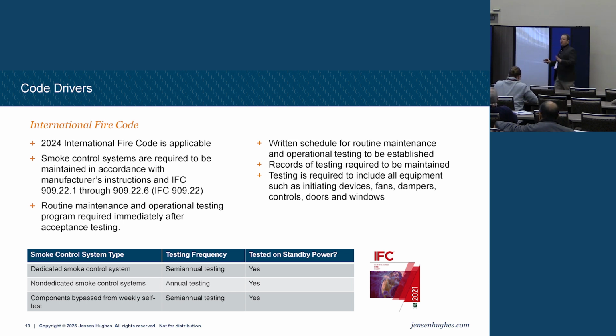Testing is required to include all the equipment, right? All the fans, all the louvers. If it opens and closes doors and you have a really busy atrium, that can be challenging during the day. So maybe we're doing this off hours now. I'm working at one in DC that is 6 or 7 massive buildings that are connected and share a large atrium, and it's all one big single fire alarm network. That building almost always we're testing it at night because there's so much volume of flow through the atrium. I can't open and close doors, and even if I can, every time I'm measuring a differential pressure and somebody opens a door in a stairwell, my differential pressure changes, right? So I'm supposed to be taking measurements during some of this. You kind of got to control that flow.